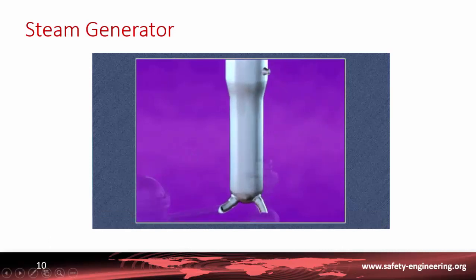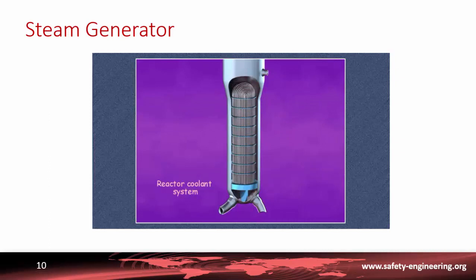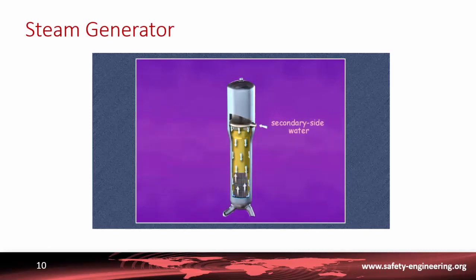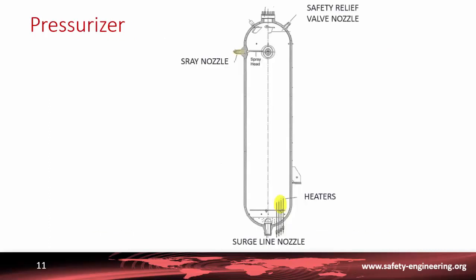In each reactor coolant system loop there is a steam generator, constituting the means of exchanging heat between the primary and secondary systems. The primary coolant from the reactor vessel enters at more than 320 degrees, circulates through a bundle of U-tubes where it gives up its heat as it is cooled by some 40 degrees, then leaves toward the pump. The secondary side water enters via the top of the steam generator, is channeled down to the bottom along the periphery, then rises up the center between the tubes, where it is vaporized. The steam produced leaves from the top of the steam generator and plays an important safety role by removing heat produced in the core.